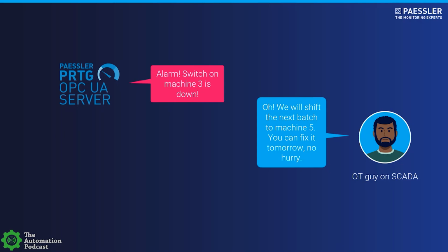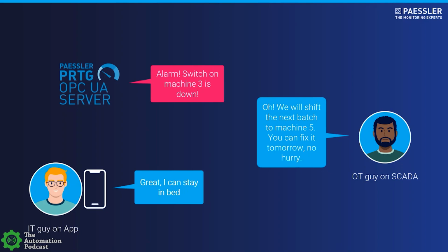And the actual benefit of having A&C is you basically have a back channel. So he can acknowledge this alarm in his SCADA system. Then the acknowledgement is of course tracked in the historian on their side, but this alarm will also be acknowledged in our system, so inside PRTG. So if there are two different users, and then we come to the IT/OT convergence thingy, both systems have an alarm, both systems acknowledge the alarm and have the acknowledgement in their tracking. That means if you do an incident follow-up later on, you will see exactly when and who actually acknowledged the alarm with this message. And that's the point. You can enter a message by acknowledging the alarm, right? I mean, that's basic. I don't need to tell you about that. But this message is then also transferred from the DCS or SCADA system back into our system.